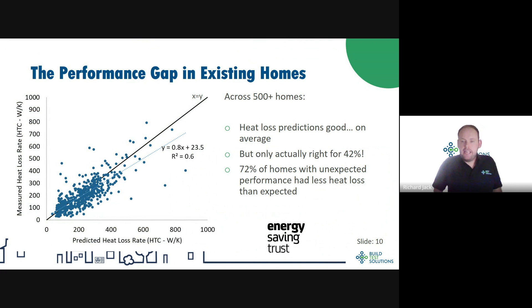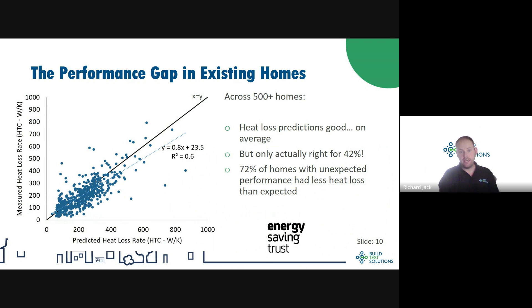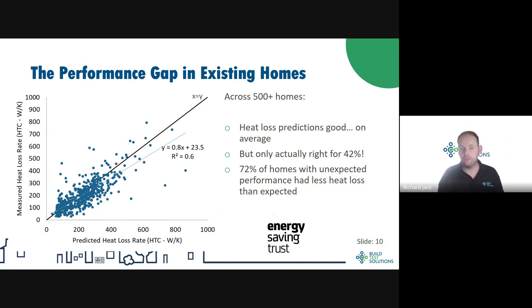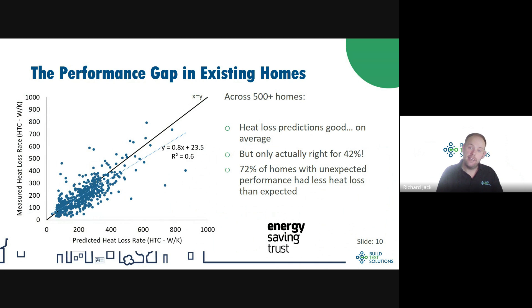Finally, instead of looking at a particular building, we're looking across a large sample — more than 500 houses — in a study we did with the Energy Saving Trust and the Department for Energy Security and Net Zero. Comparing predicted heat loss on the x-axis against measured heat loss for those buildings, we see there is a clear relationship: the predictions aren't complete nonsense — they are on average classifying best, middle, and worst performing houses — but there's lots of variation for particular houses. The prediction is good on average but not very good for thinking about a particular building.